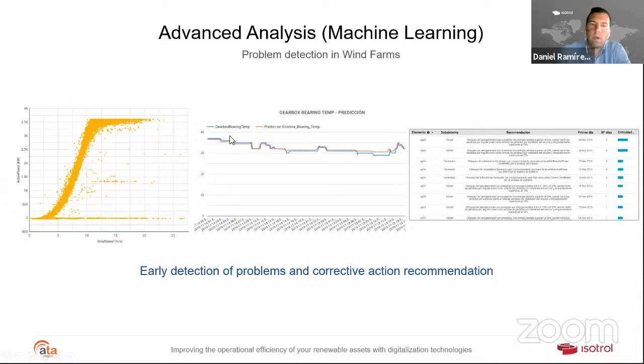Here we're comparing the bearing temperature of one of the wind turbine gearboxes with others, comparing it with historic data to predict what's happening in the turbine. We might not have an alarm, even a warning alarm, but the turbine might be heating up more than any other wind turbine in that wind farm. So it's worth setting thresholds to analyze and predict when something could be leading into a failure mode or failure direction.